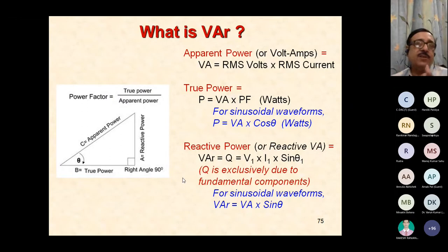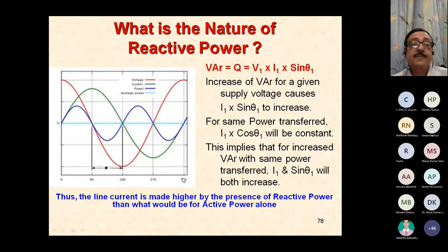We do not talk much about distortion in voltage because voltage distortion most of the time is less than 3%, which is quite small. But the current distortion can achieve very large magnitudes. So I have taken an example of voltage and current displaced by 90 degrees intentionally so that there is no active power involved and everything is reactive power. When you plot instantaneous voltage into current, you find that it is expressed in the blue line, which shows an equal area between the positive and negative half cycles, so that the average power transferred during this process is zero. You don't have any average power transferred, but you have something called reactive power. So the line current is made higher by the presence of reactive power than what would have been with active power alone.